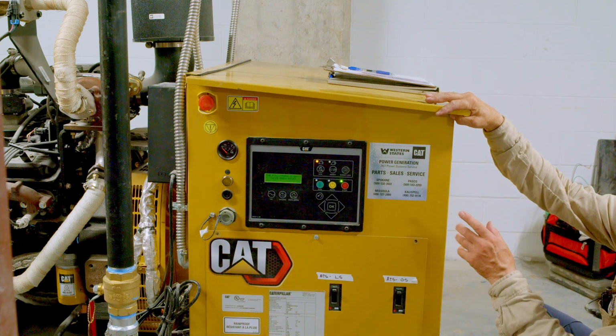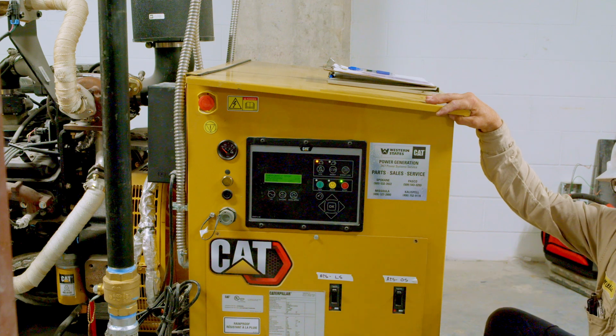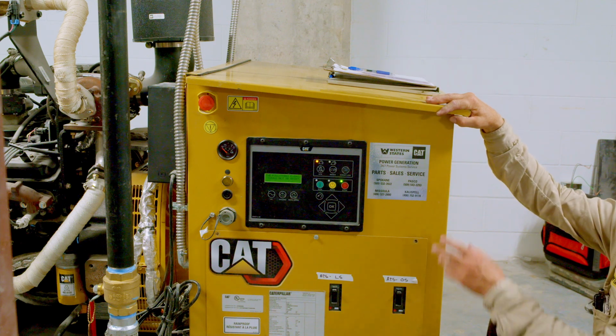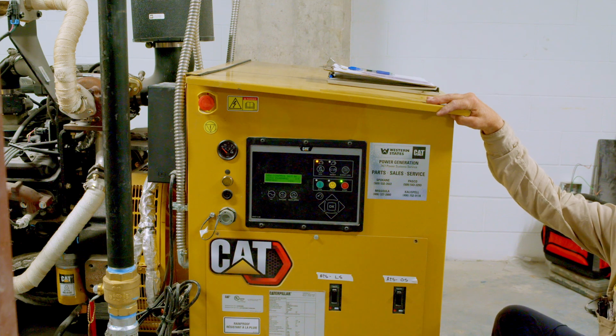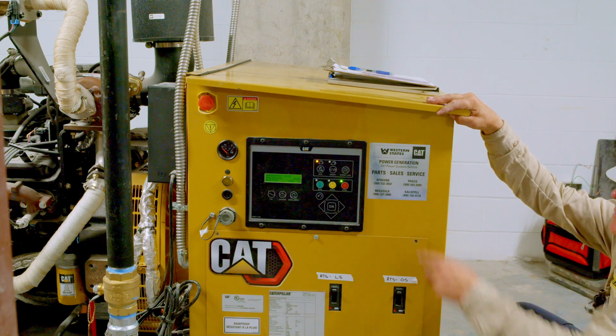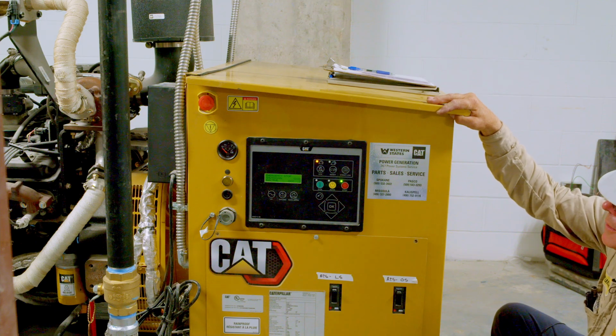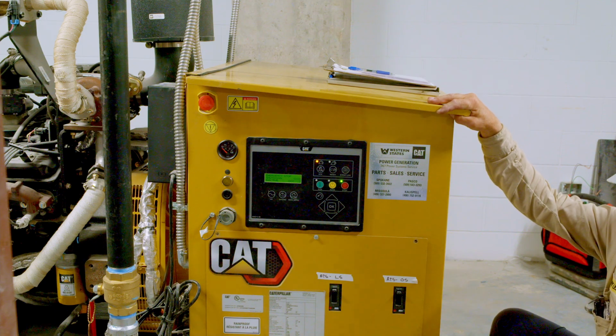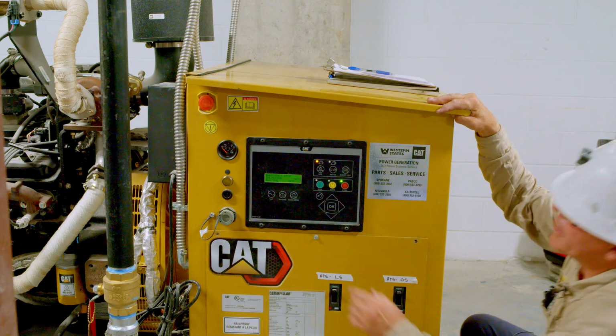When the unit is shut down, you cannot see coolant temp or oil pressure. It's not communicating with the engine until it gets a crank output from this genset controller. So I'd recommend, like with a coolant heater, just to put your hand on it, because right now you can't see what it's doing.